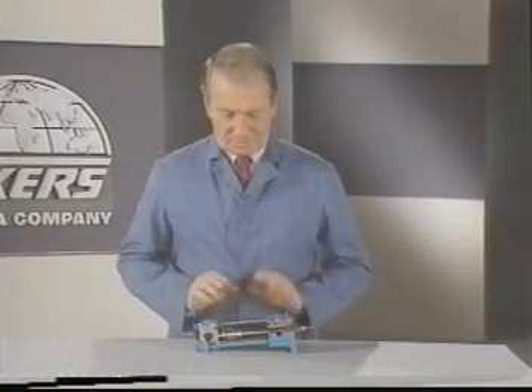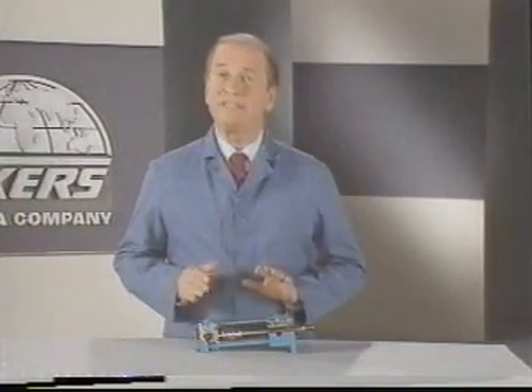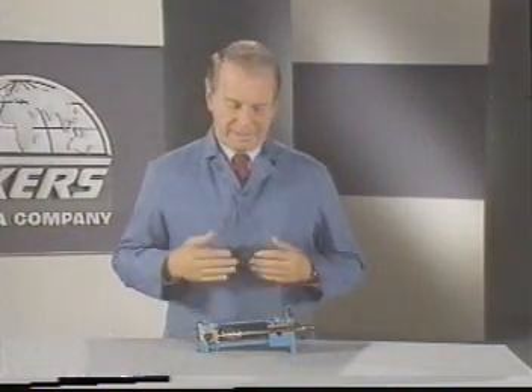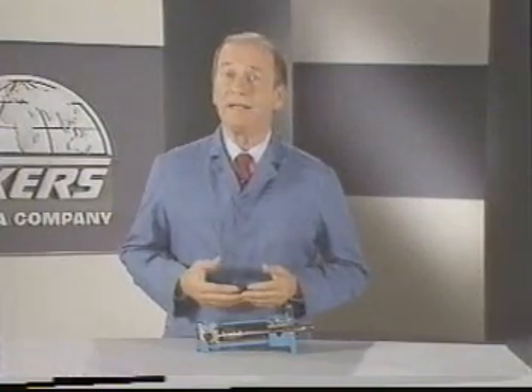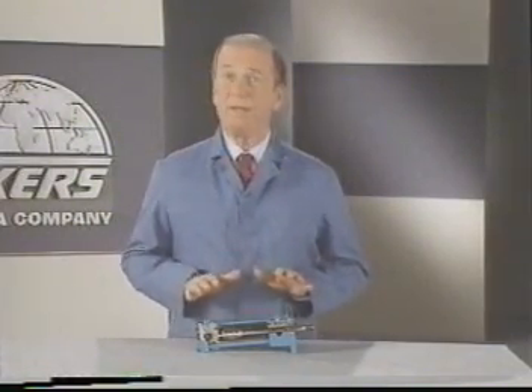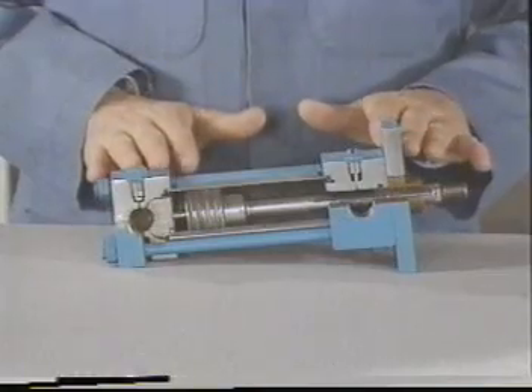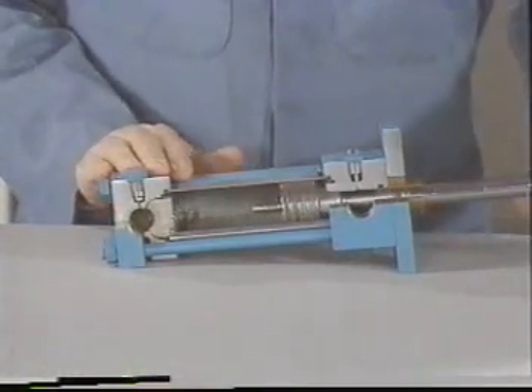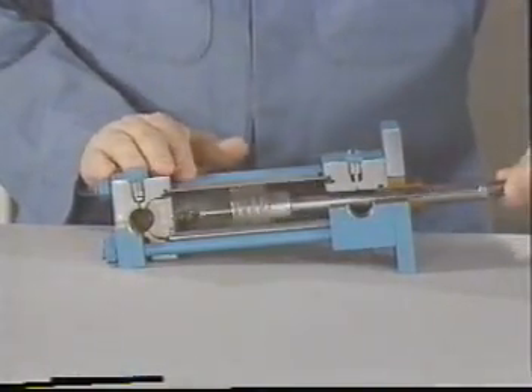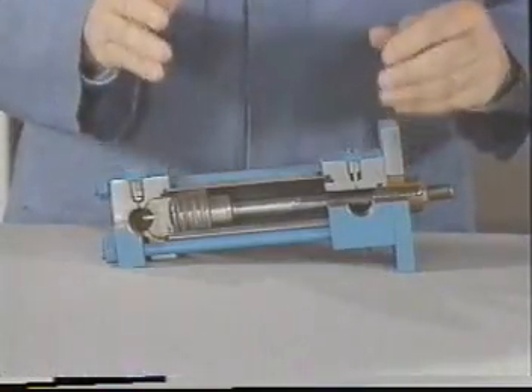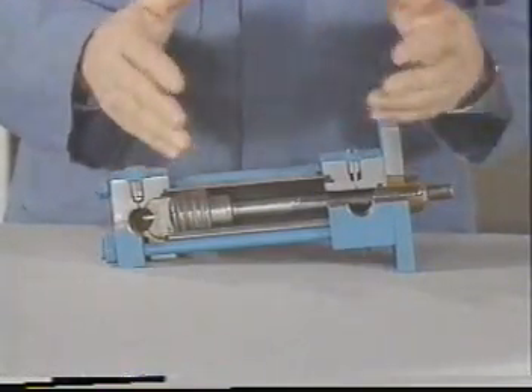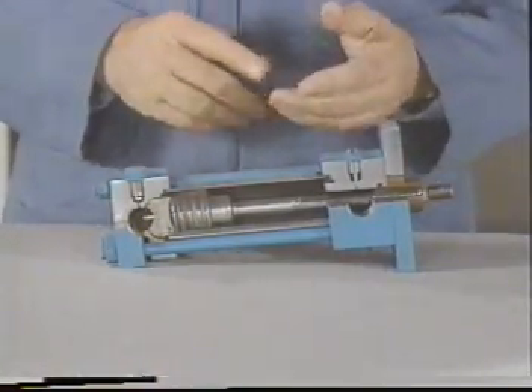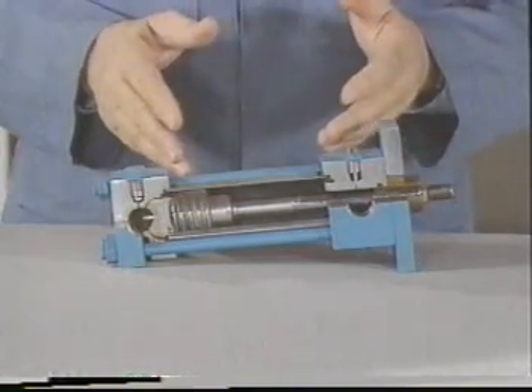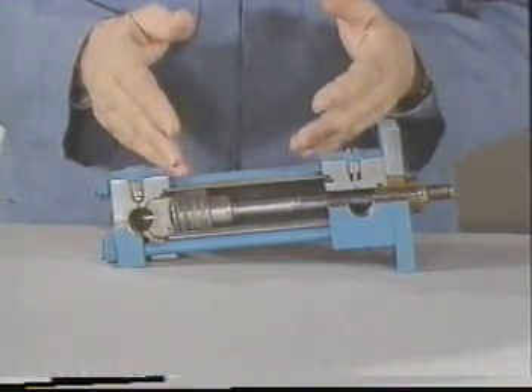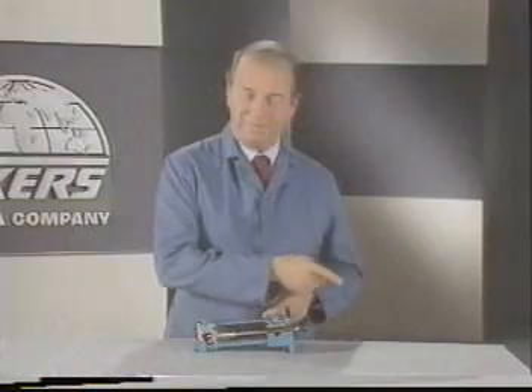A cylinder or linear actuator provides the straight line motion. It can be single acting like a hydraulic jack where the weight of the car brings it back down, or double acting where the piston is forced both forward and backward in its bore by fluid under pressure. A rod connected to one side of the piston extends from one end of the cylinder to the part to be moved. Now, here's another point to remember.